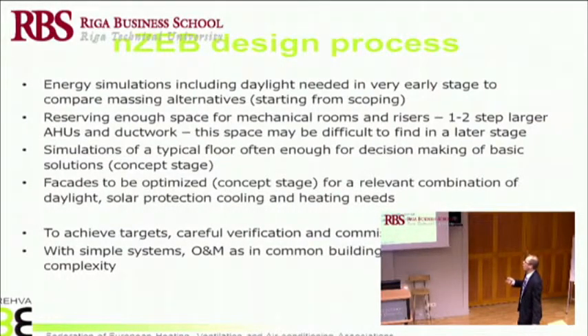And what has been a real problem in such buildings is that it's difficult to reserve enough space for mechanical rooms and risers, for the ductwork. If this is not done at a very early stage, you cannot find this space for the systems anymore at later stages, so this really needs to be considered, including for the effective air handling units, which are quite large and need a lot of space.